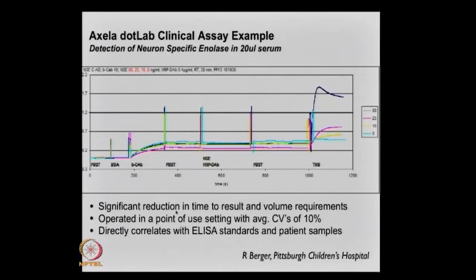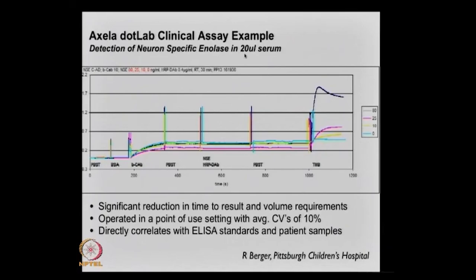Here is one of the early clinical examples using the commercial instrument. Now that there is an instrument others can use, people can configure their assay and work out how to get it to work best. This is the detection of neuron-specific enolase, which is associated with traumatic brain injury. Dr. Berger was using this primarily to look at markers in babies — when babies have shaken baby syndrome. Being able to use only 20 microliters is very important because you cannot get too much blood from babies.